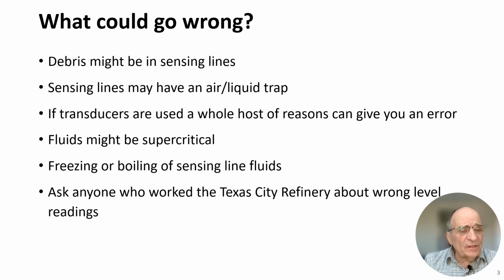Fluids might be supercritical. Well, if the fluid is supercritical, you're not going to get any difference in density between the liquid and vapor. So level controllers just won't operate, because the density of the liquid and the density of the vapor are the same. There is no actual liquid and vapor. There's just a supercritical fluid. Freezing or boiling of the sensing lines is a concern. Ask anyone who worked at the Texas City refinery about wrong level readings, and we'll show you what happened at the Texas City refinery.